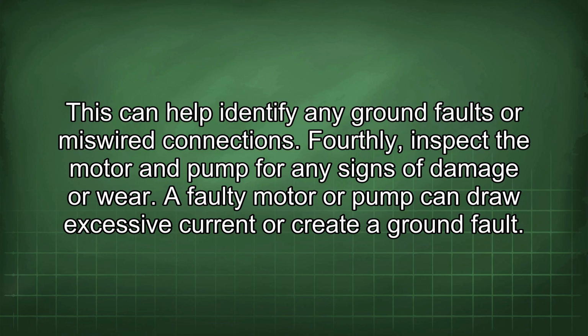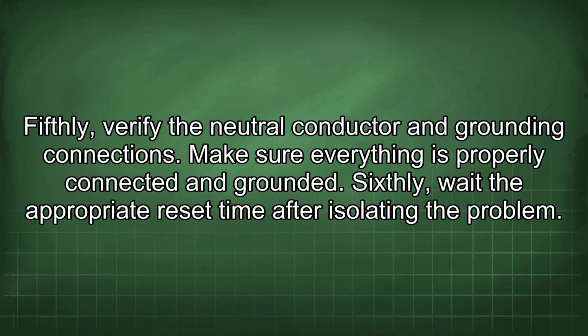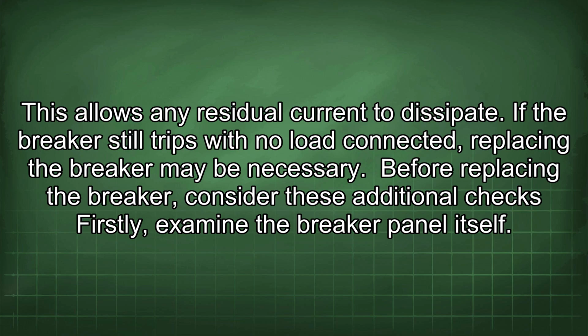Fourthly, inspect the motor and pump for any signs of damage or wear. A faulty motor or pump can draw excessive current or create a ground fault. Fifthly, verify the neutral conductor and grounding connections. Make sure everything is properly connected and grounded. Sixthly, wait the appropriate reset time after isolating the problem. This allows any residual current to dissipate. If the breaker still trips with no load connected, replacing the breaker may be necessary.